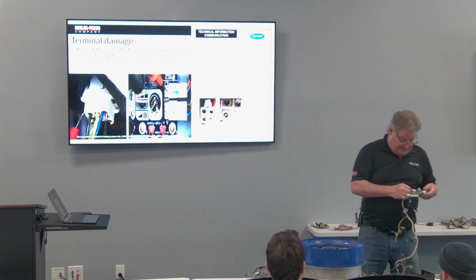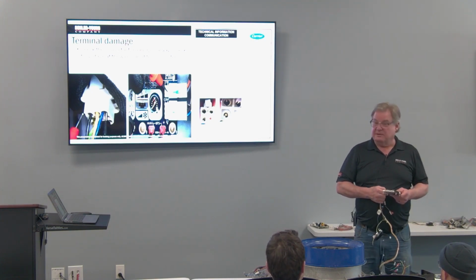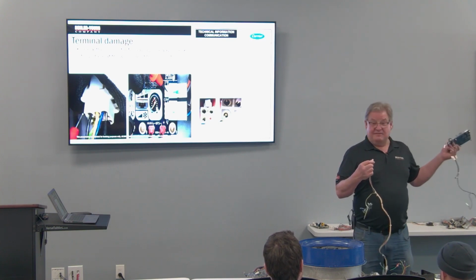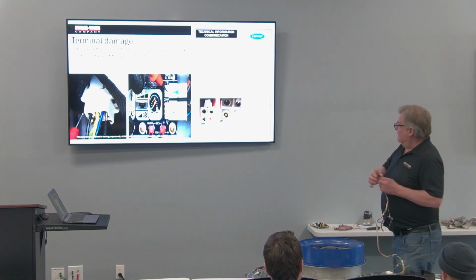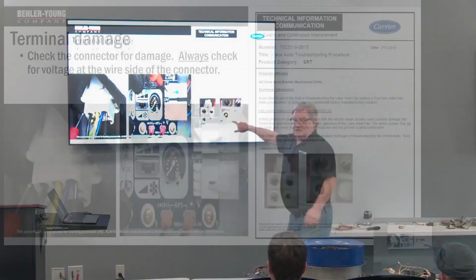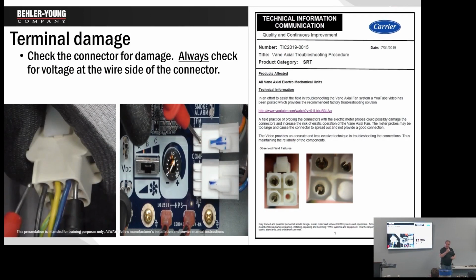So you might have to get some needle leads. So what the contractor had done is the motor wasn't coming on because he didn't have it set up right. So it kept cutting out. So you unplug this. Remember I said I'd have Dave come slap you if you stick your meter leads in the front? Well, he did. So that plug you see right there is this plug. And you can see he jammed his meter leads into the front of that, mushroomed them all out.